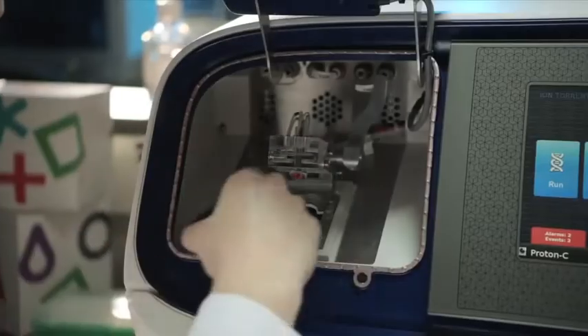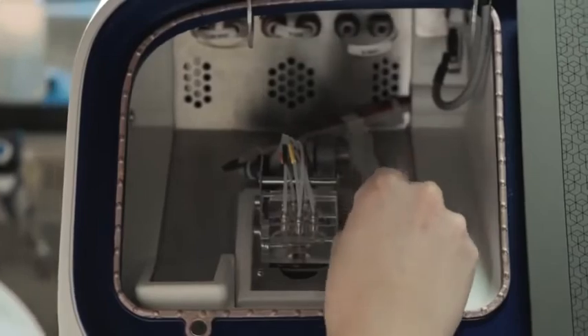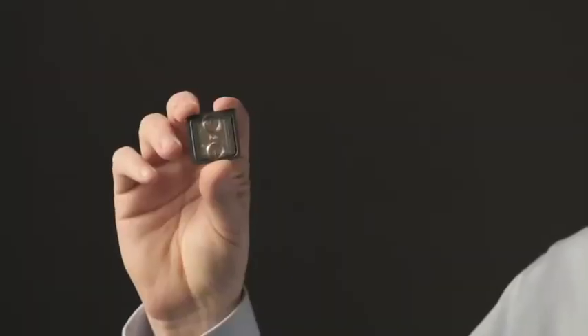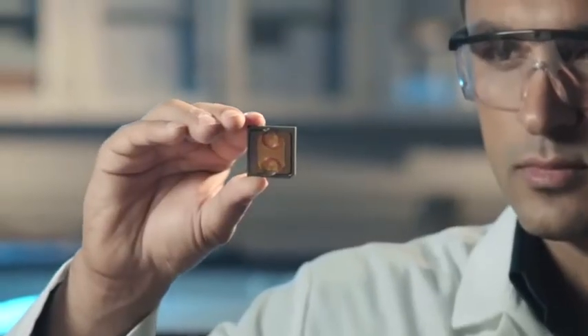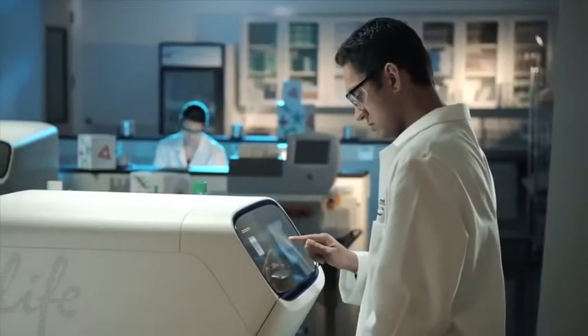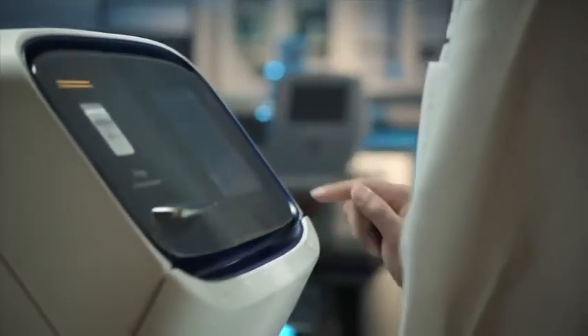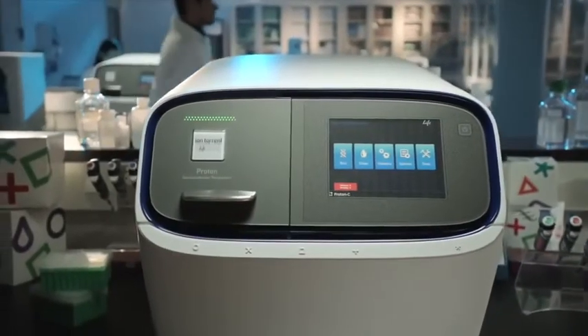The Proton2 works at the core by semiconductor sequencing. And the beauty of semiconductor sequencing is it's really as simple as a CMOS chip. Every teenager who has a smartphone or camera phone, you've got a little CMOS chip, and that chip has thousands of pixels that measure the intensity of light coming in to generate a photo. But instead of a sensor for light, it's a sensor for chemistry. And it's really this first sort of crossing the divide of chemical into digital information.